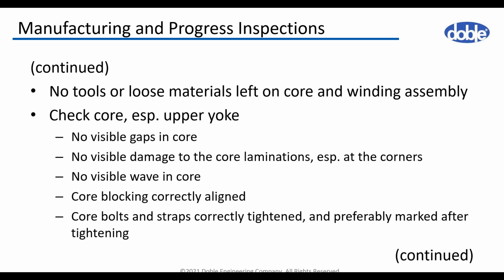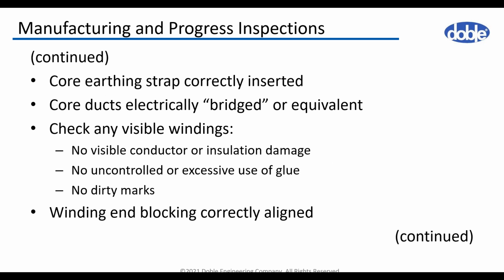We check the core, and especially the top yoke, for gaps between the laminations and damages on the laminations, as well as the core for typical places where you can find damages. These are the tips. Also, we check visibly if the core blocks are correctly aligned. We also check the core bolts or straps if they are tightened correctly and marked. The correct grounding of the core frame is very important in order to avoid issues during service, and because of this we check if the core ground straps are inserted correctly. The cooling ducts or different sections of the core should be bridged accordingly.